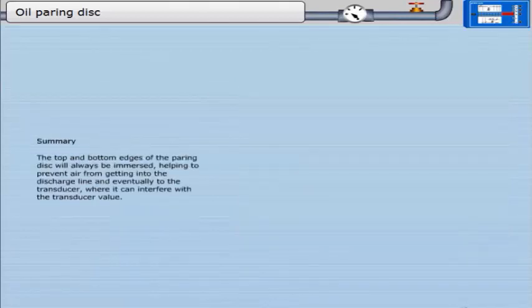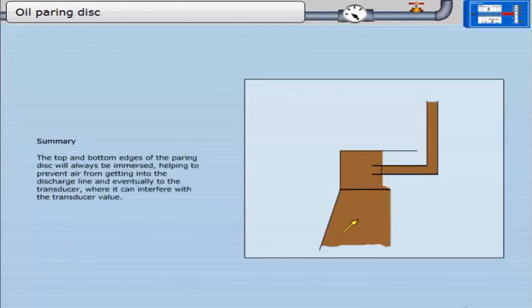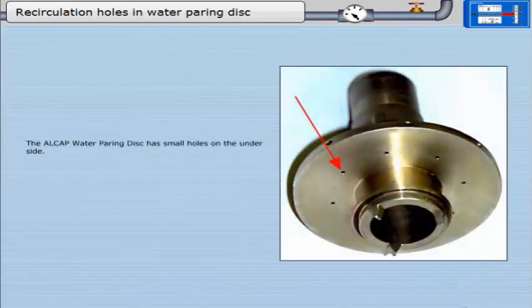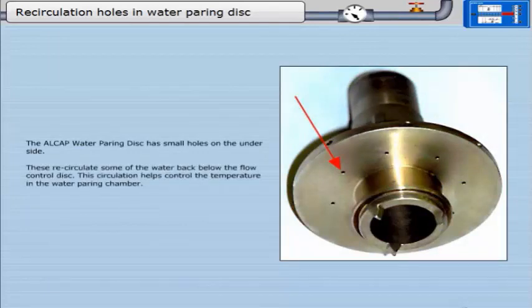The top and bottom edges of the paring disc will always be immersed, helping to prevent air from getting into the discharge line and eventually to the transducer, where it can interfere with the transducer value. The Alcap water paring disc has small holes on the underside. These recirculate some of the water back below the flow control disc, which helps control the temperature in the water paring chamber.